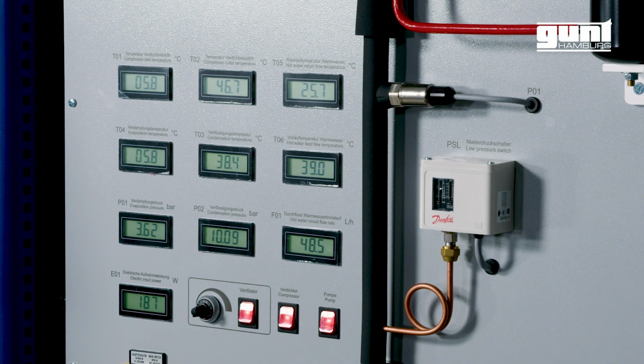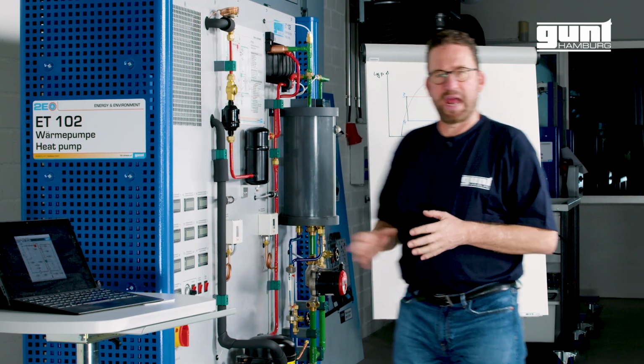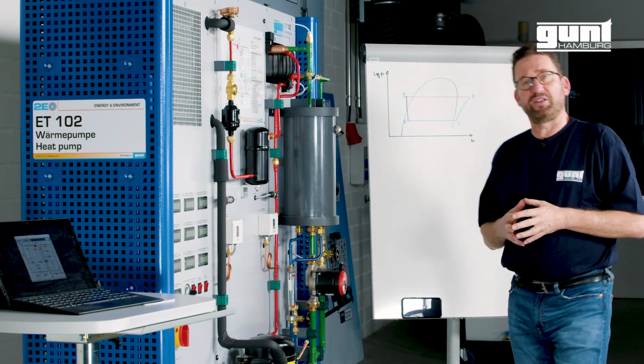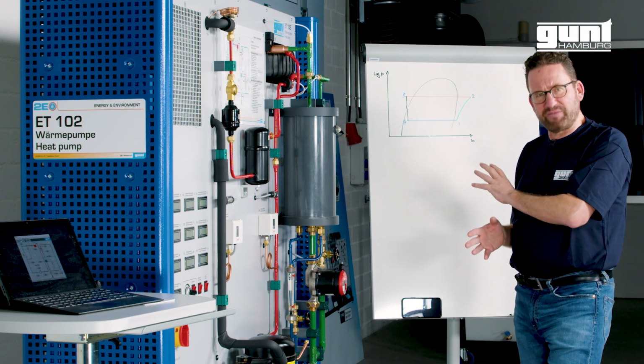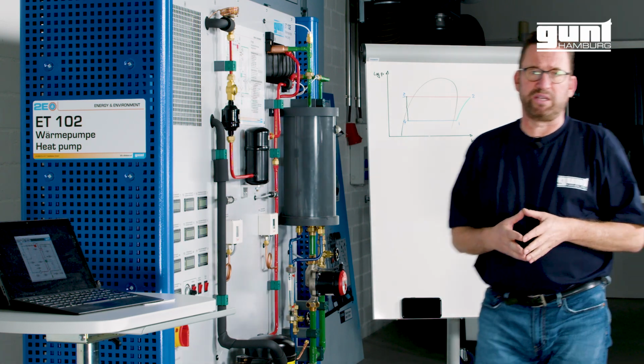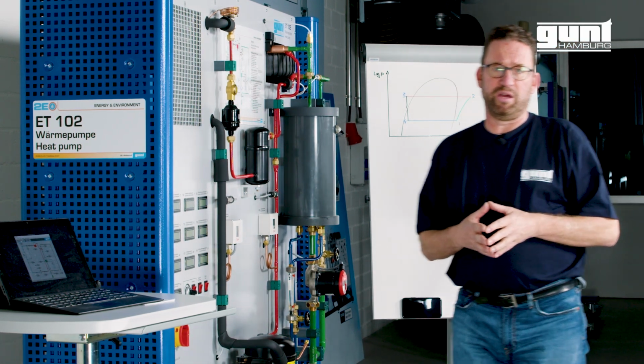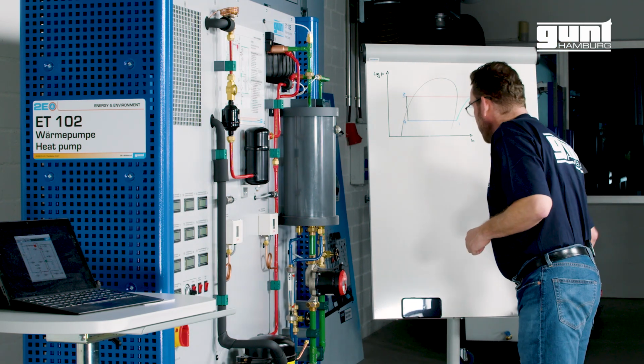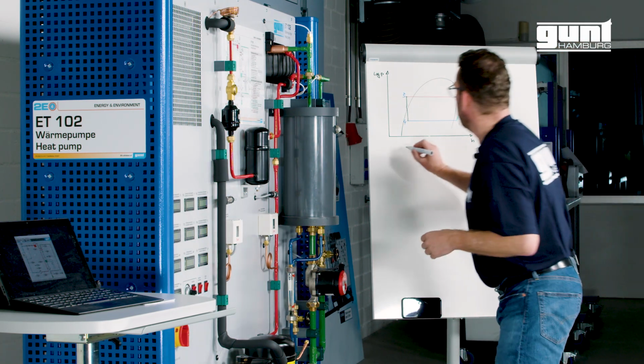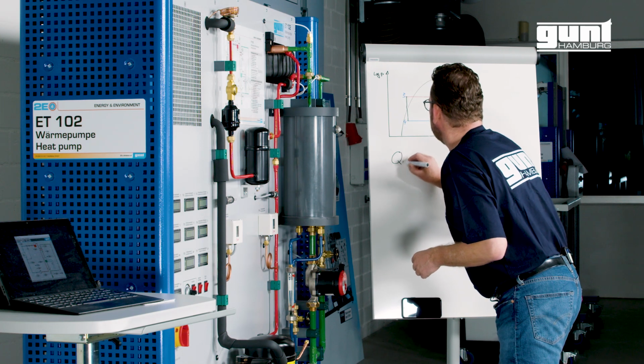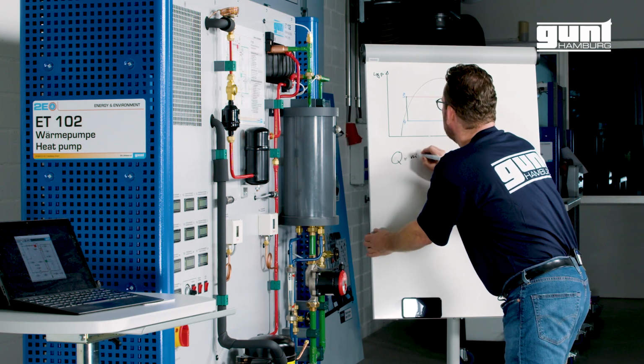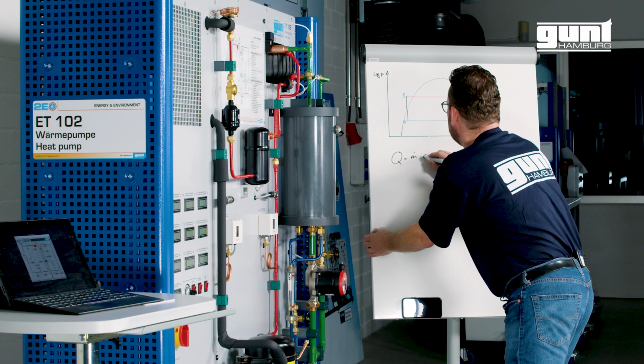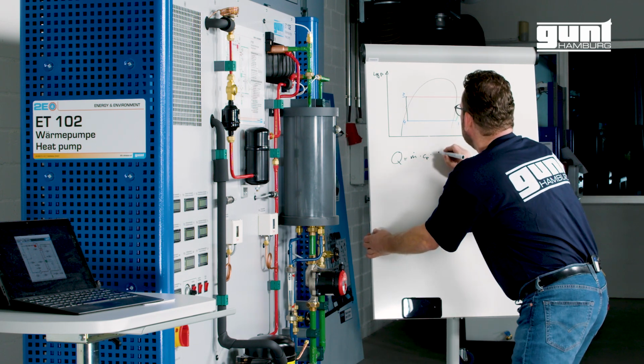With the experiment data that we have gathered from the displays, we can now manually calculate the heat discharge from the unit and compare that value to the value that's coming out of the data acquisition system on the PC. So let's get started.